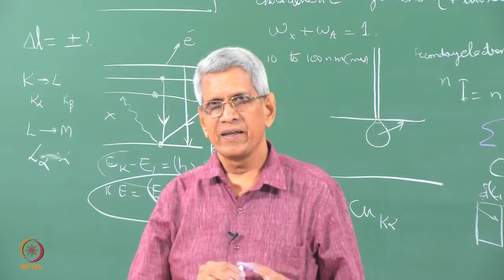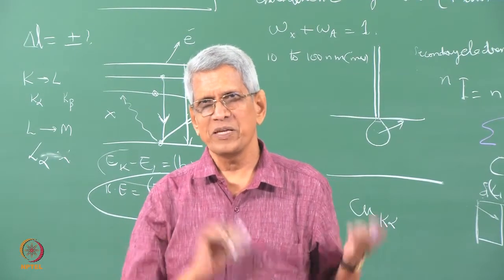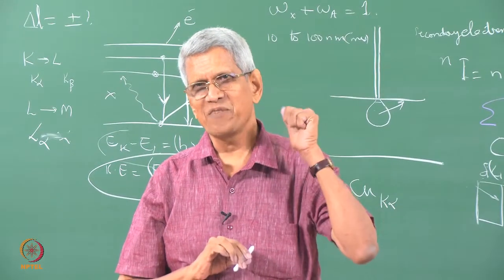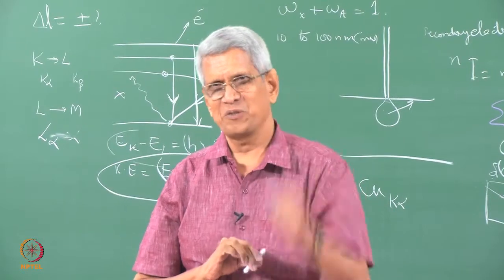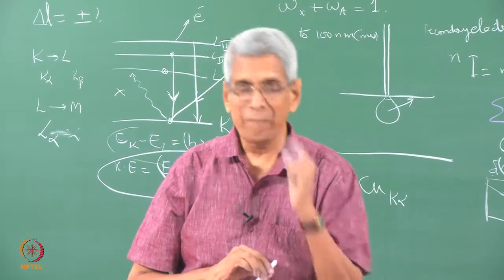In the case of germanium it is 2.5 electron volt which is required. Okay. That means that for the same energy of the X-ray, the number of electron hole pairs which will be generated is more in germanium, so the sensitivity is high for germanium. So if one can afford to use that, that is good, though it is expensive. Okay.